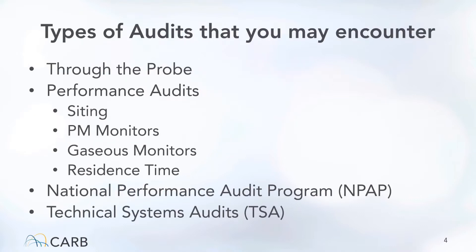As site operators, there are a few types of audits that we may encounter. Number one, through the probe — typically auditors will feed a known concentration of pollutant into your sampling system at your inlet. This is the best way to simulate ambient sampling when you are in the field.